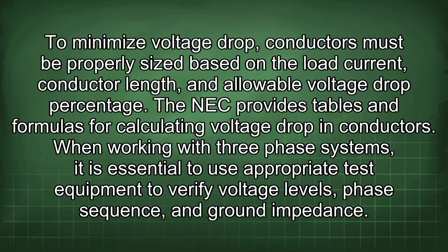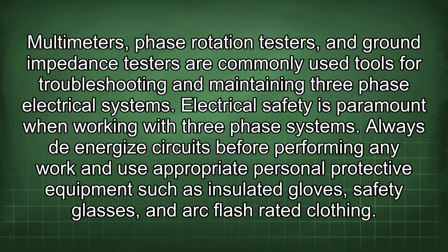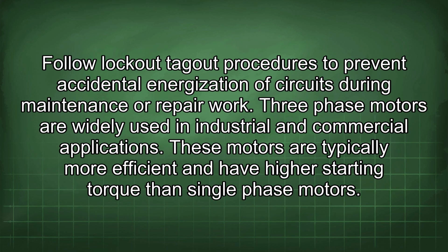When working with three-phase systems, it is essential to use appropriate test equipment to verify voltage levels, phase sequence, and ground impedance. Multimeters, phase rotation testers, and ground impedance testers are commonly used tools for troubleshooting and maintaining three-phase electrical systems. Electrical safety is paramount when working with three-phase systems. Always de-energize circuits before performing any work and use appropriate personal protective equipment such as insulated gloves, safety glasses, and arc flash-rated clothing. Follow lockout-tagout procedures to prevent accidental energization of circuits during maintenance or repair work.